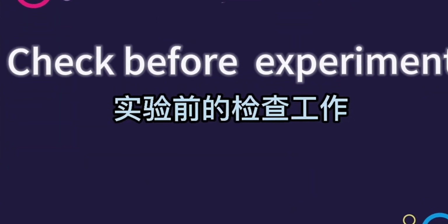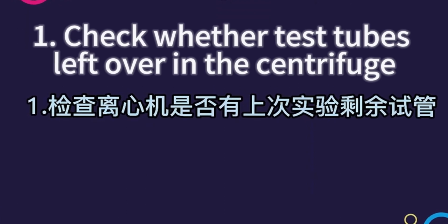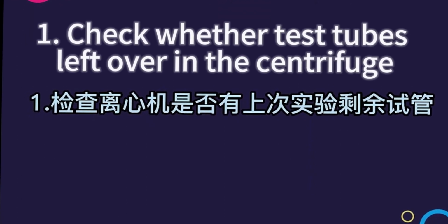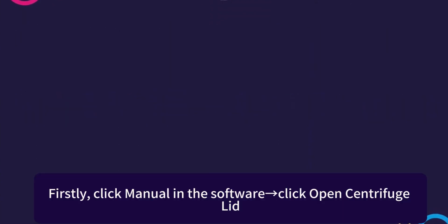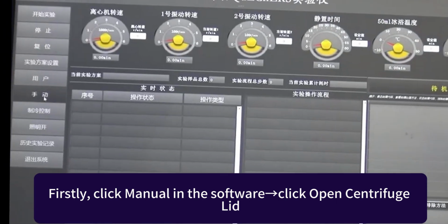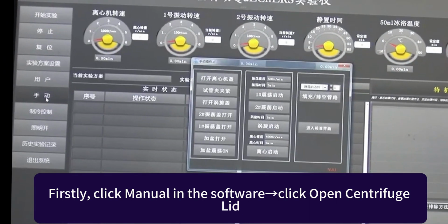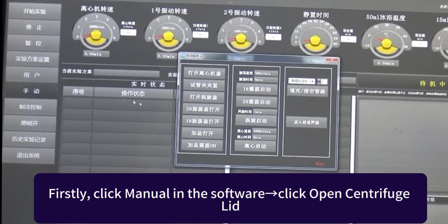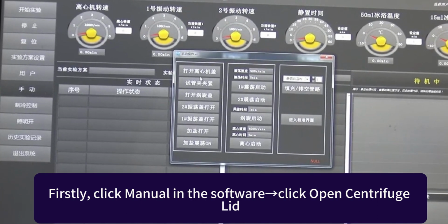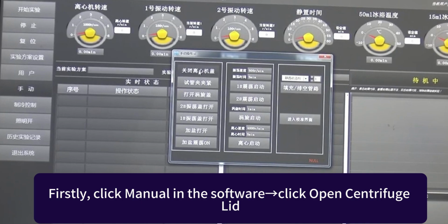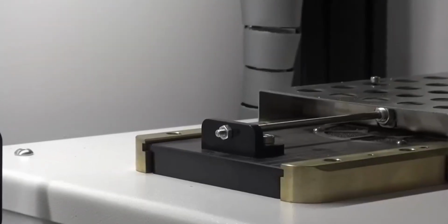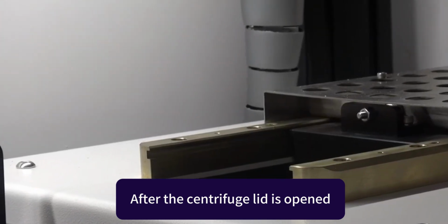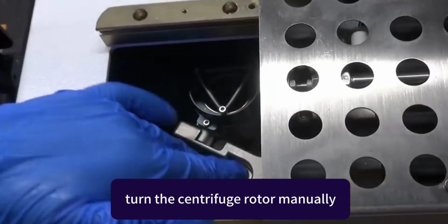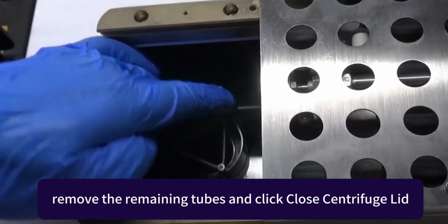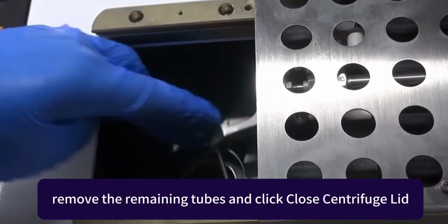Check before the experiment. 1. Check whether test tubes are left over in the centrifuge from the last experiment. Firstly, click Manual in the software, click Open Centrifuge lid. After the centrifuge lid is opened, turn the centrifuge rotor manually, remove the remaining tubes, and click Close Centrifuge lid.